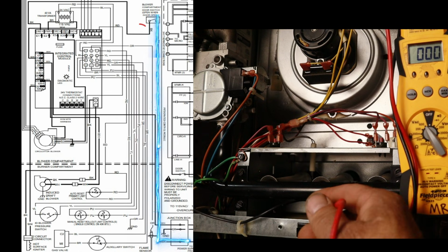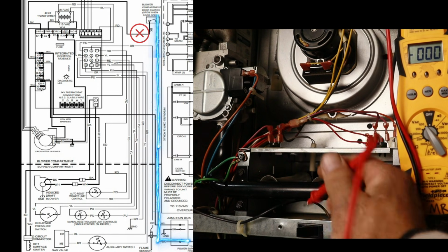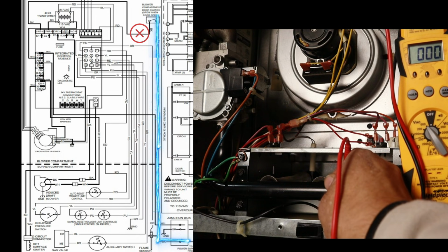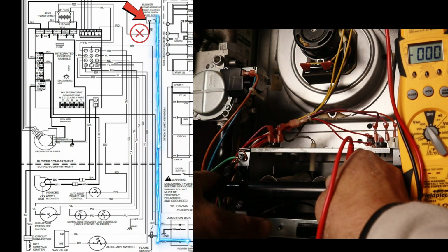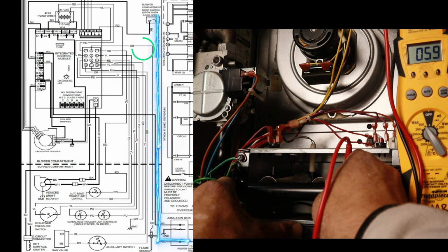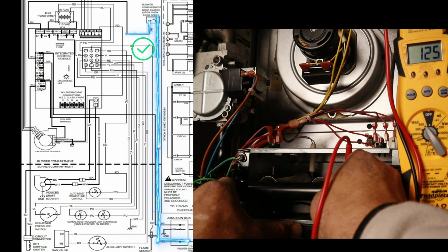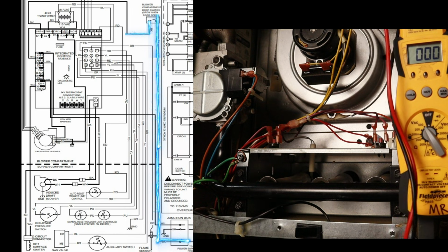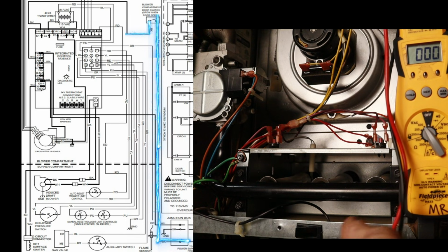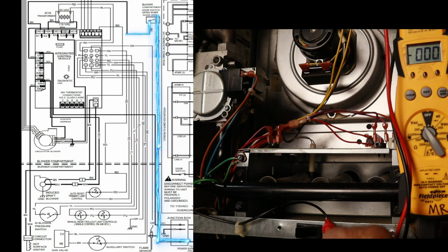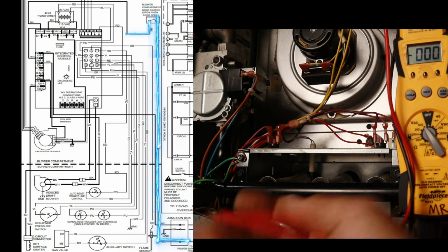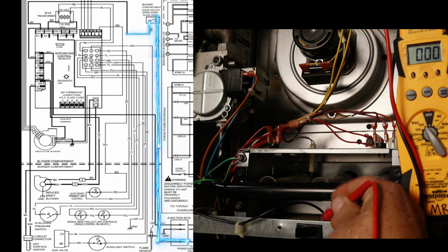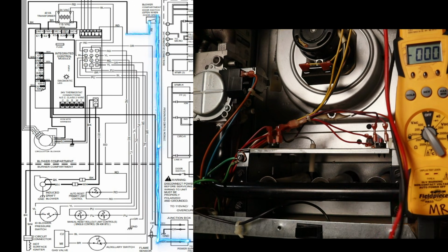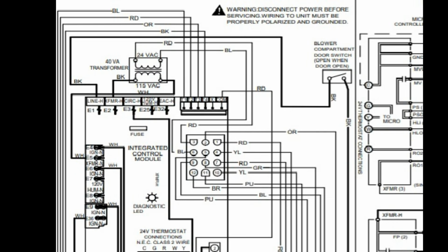Now this door switch is going to break that circuit because I have the door off. So if I were to test the other side of that switch to ground, you can see I'm reading nothing. But as soon as I push that door switch in, the switch is now allowing the 125 volts through, and it is carrying on to the rest of the unit. So just by looking at this schematic and learning how to read it and trace the power in, I've just figured out how to diagnose a door switch. So if I have 115 coming in but not coming out when this switch is pushed closed, I have a bad door switch. So coming back to our schematic, we can trace that black wire coming out of our door switch and see where it goes from there.